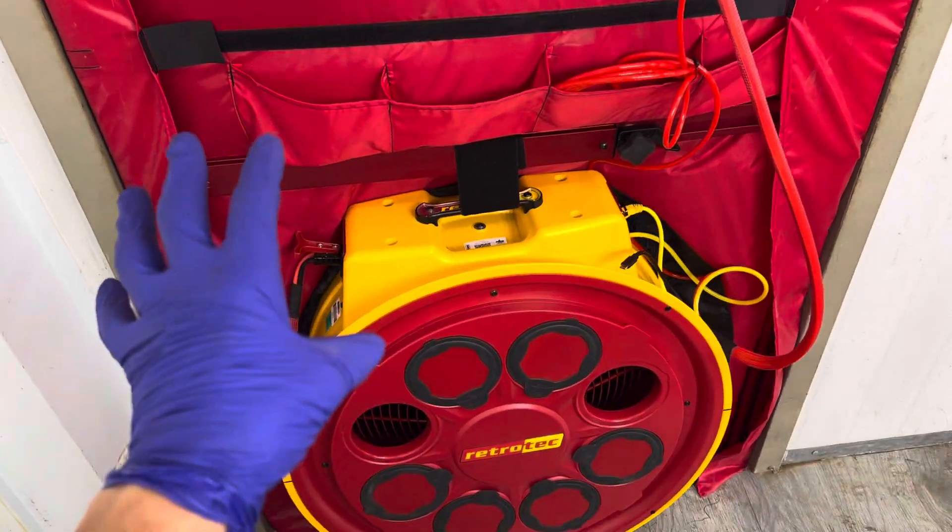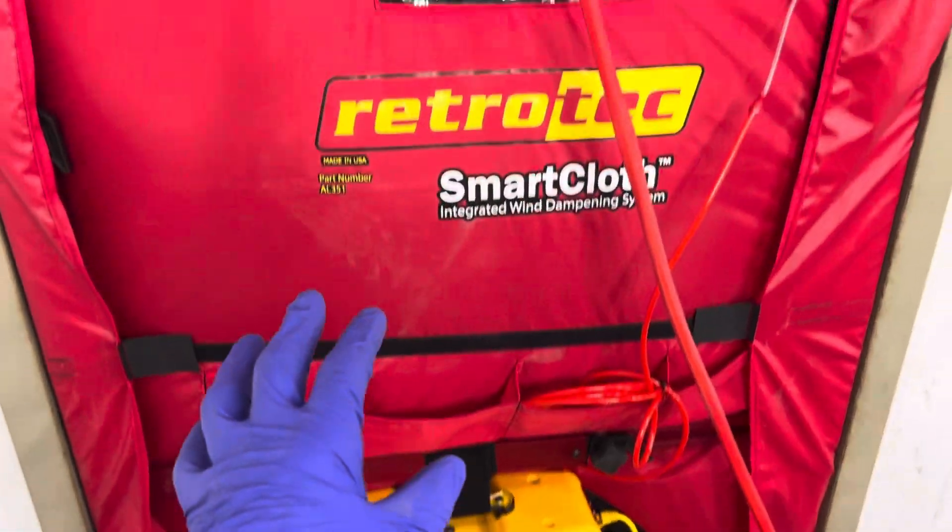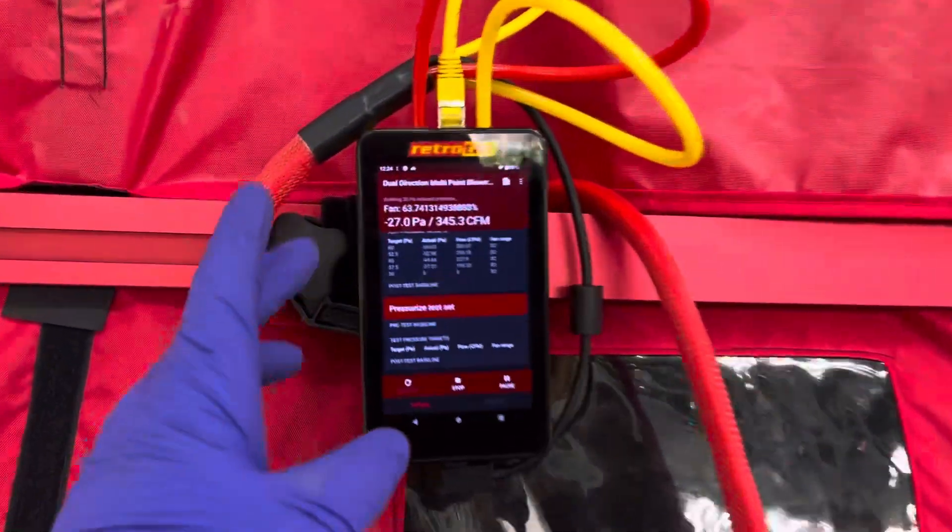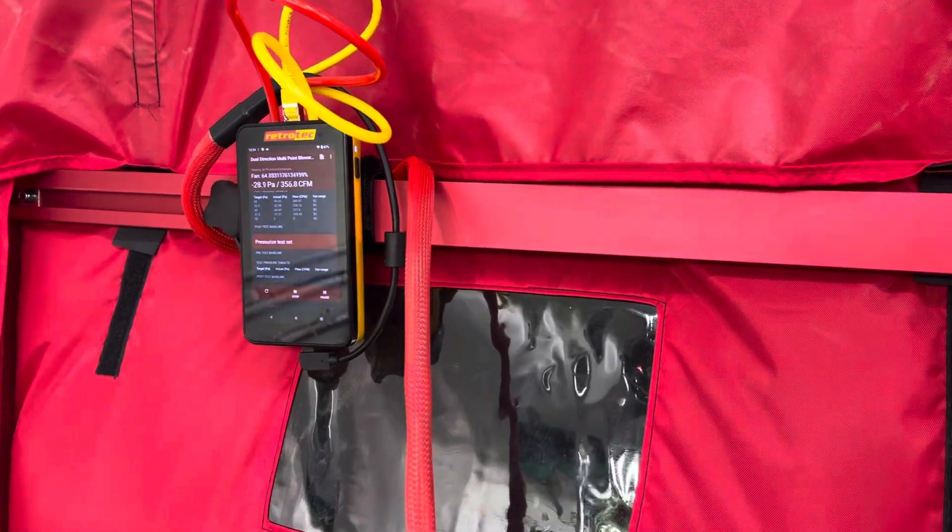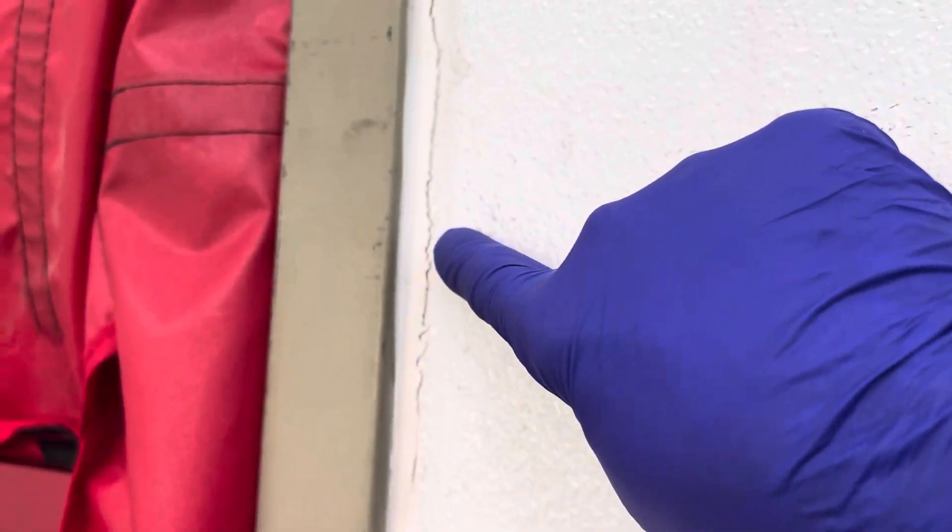So performing a pressure and depressurization test, blower door test, not only do you find what rating you're at, but little things like this. You see that little tiny crack? When I put my arm right here, I'm being hit with cold air.